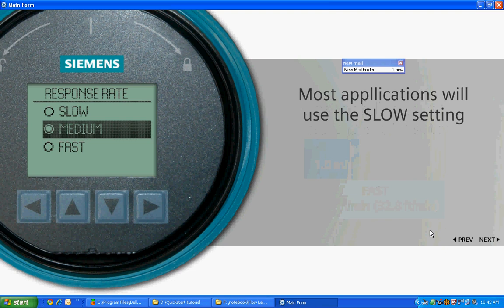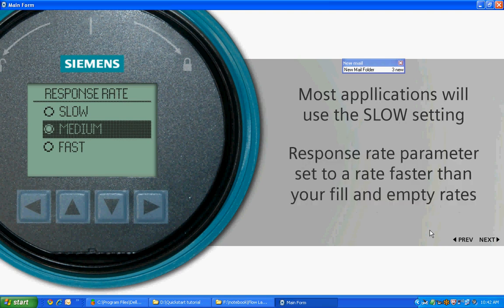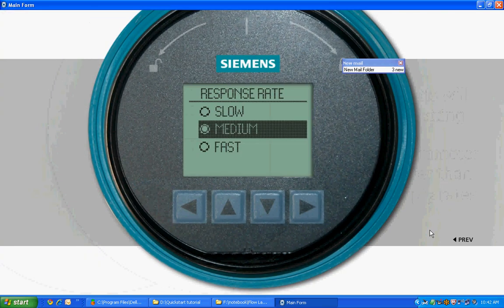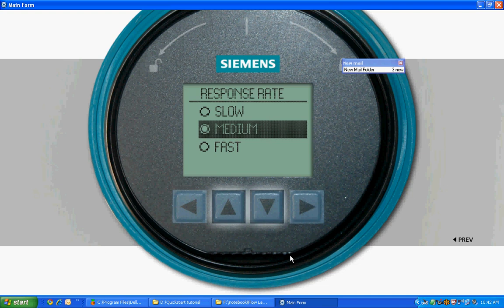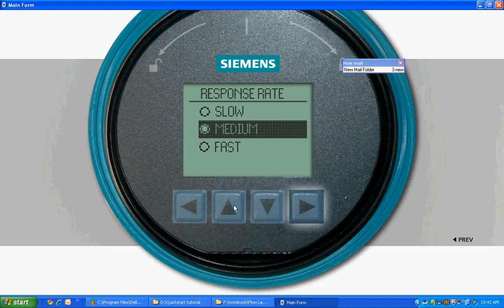Set the response rate parameter to a rate that is faster than your fill and empty rates. Please use the up and down arrows to select your option. Press the right arrow to save your choice. And press Next to proceed to the sensor units parameter.